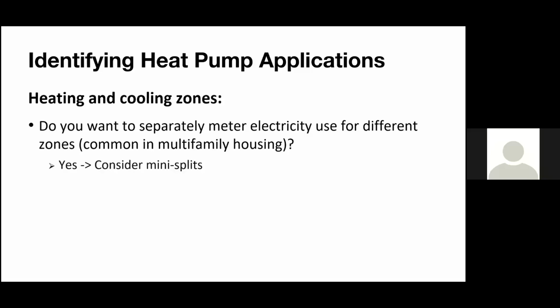There are other solutions for VRF systems. Let's say you did install a VRF system and it's feeding 20 apartments. There is energy allocation out there, which basically meters and takes into consideration how many kilowatts are being used at each fan coil unit. However, right now in Massachusetts, it's a little foggy subject. Legislation is still working on it to make it approved. Places in New York City and Rhode Island use energy allocation all the time for tenant billing, as they're using VRF systems. But anyways, if an owner did say, hey, look, I'll put it in the rent, then you kind of have a free for all. If you want to use a VRF system, you can.